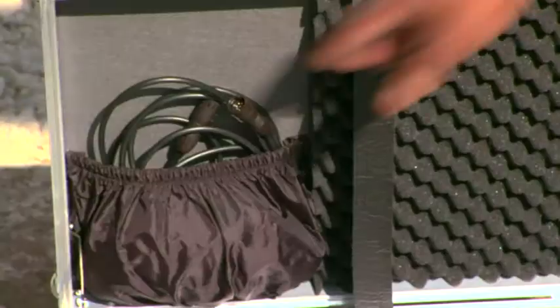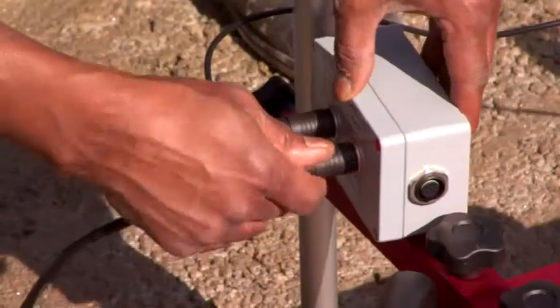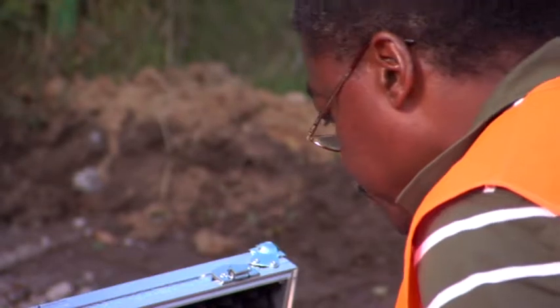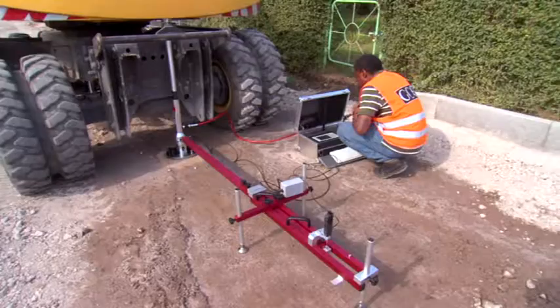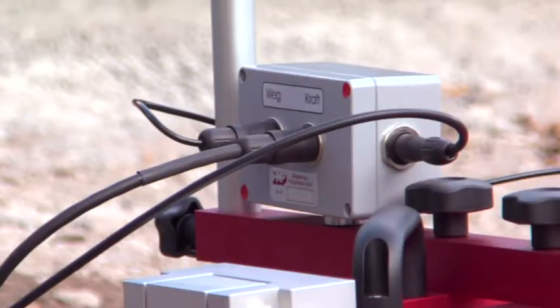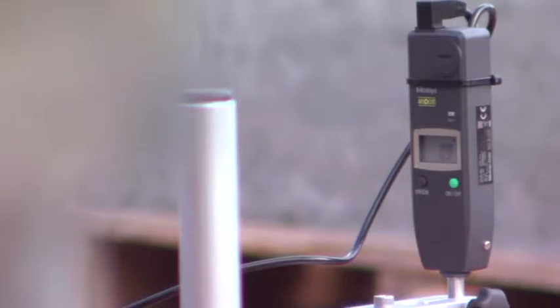An excellent innovation is the use of a specifically designed measuring head, which brings the measurement results for path and force together via the support frame. The measuring head guarantees a digital and interference-free transmission of force and settlement values to the measuring mechanism.